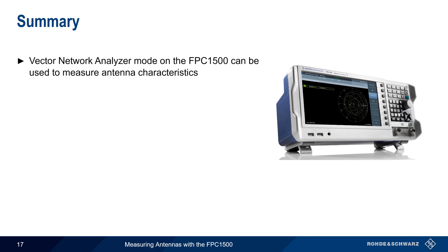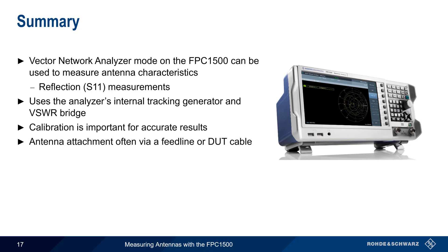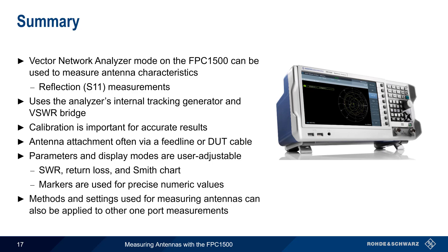Let's end with a brief summary. Vector Network Analyzer mode on the Rohde & Schwarz FPC-1500 spectrum analyzer can be used to measure antenna characteristics by performing reflection or S11 measurements. These are made using the analyzer's internal tracking generator and VSWR bridge, meaning that no external devices or accessories are needed. However, one-port calibration is needed before making measurements, requiring either manually attached calibration standards or an automatic calibration unit. Keep in mind that a feed line and/or DUT cable are often connected between the FPC and the antenna under test. Measurement parameters and display modes are user adjustable — the most common being standing wave ratio, return loss, and the Smith chart. Markers can be placed to obtain precise numeric measurements. Although this presentation has been focused on antenna measurements, the methods and settings used can often also be applied to other one-port devices.